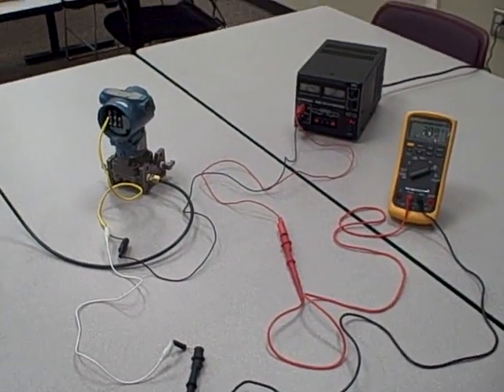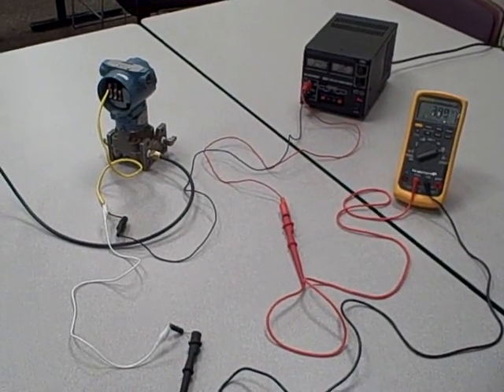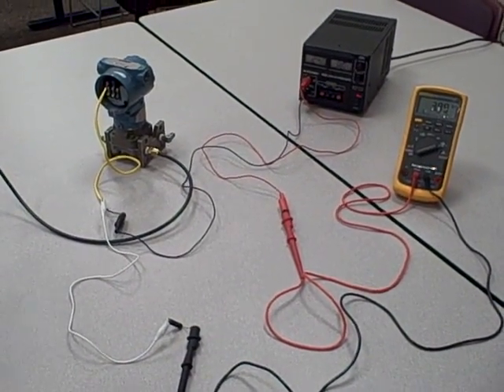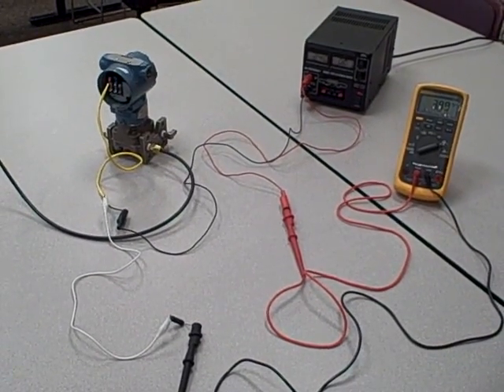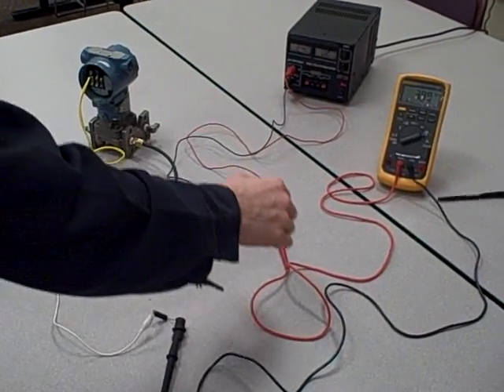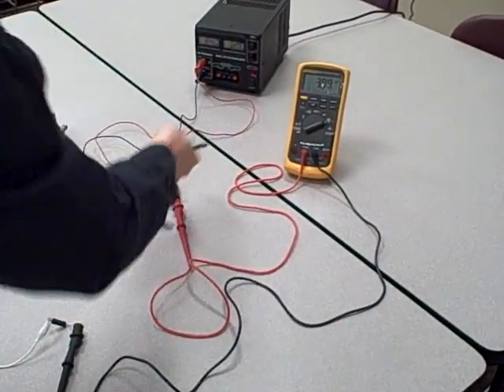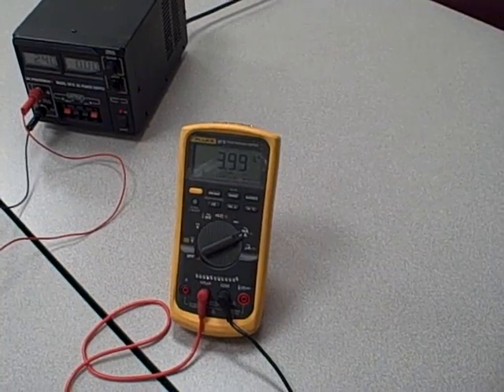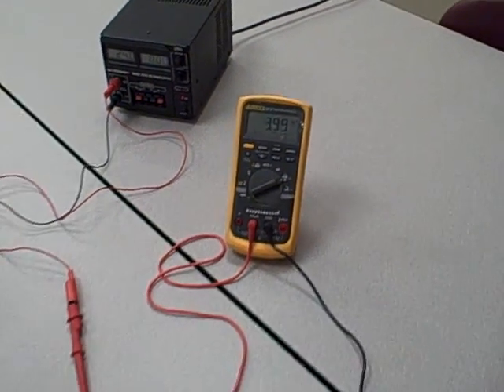We're going to do a simple exploration of 4 to 20 milliamp current loop and how this transmitter responds to pressure. The range of the transmitter currently is 0 to 1,000 inches of water pressure and we are currently measuring 0% which is a 4 milliamp signal. It says 3.99 on the meter but we're supposed to be at 4 milliamps. Close enough for a test.